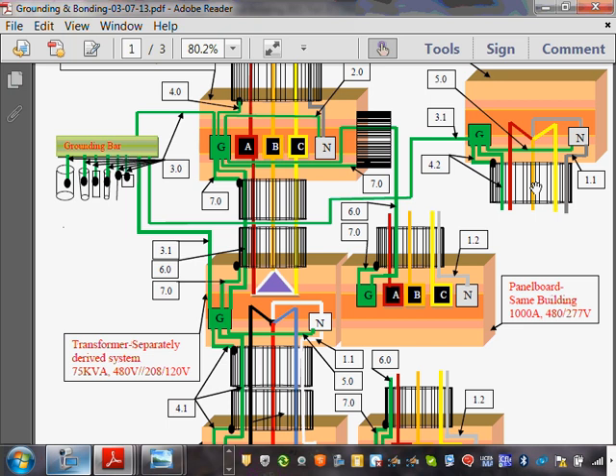Regardless of whether you're running a separately derived system or a non-separately derived system, your generator is feeding a grounded system. 95% of the time you have a generator feeding a grounded system. You're not feeding a delta, right? You have to have a neutral. I've seen drawings where they have a generator and they're only bringing three-phase wires to the. That's 13.8. You're maybe talking about 13.8, like 13,800 volt high voltage, or a delta generator, an ungrounded delta system.